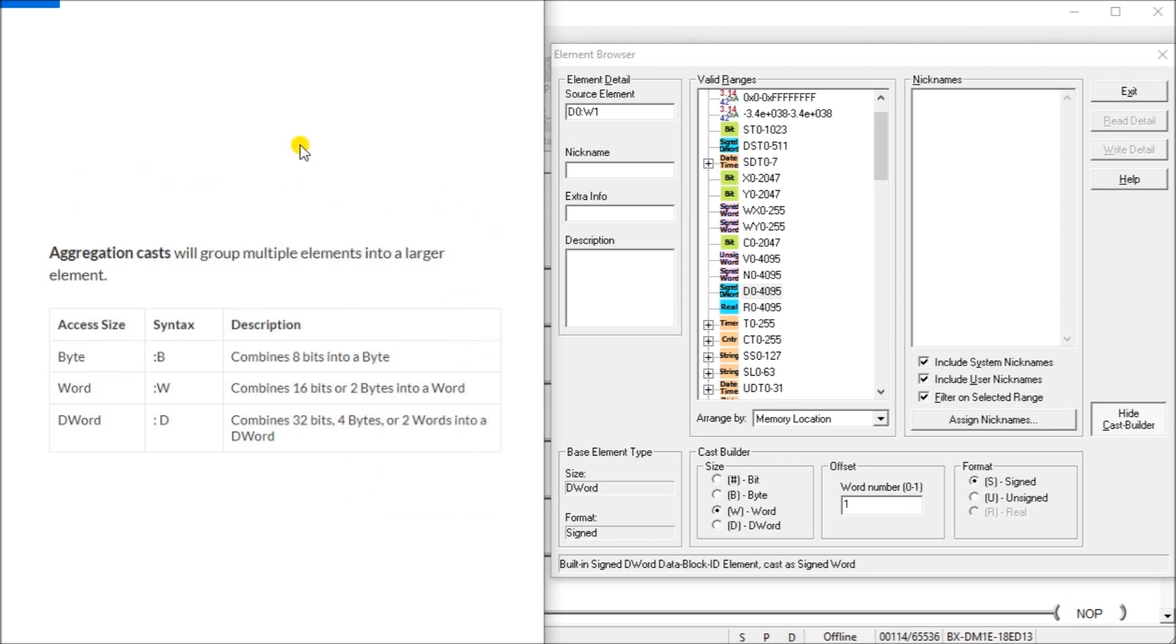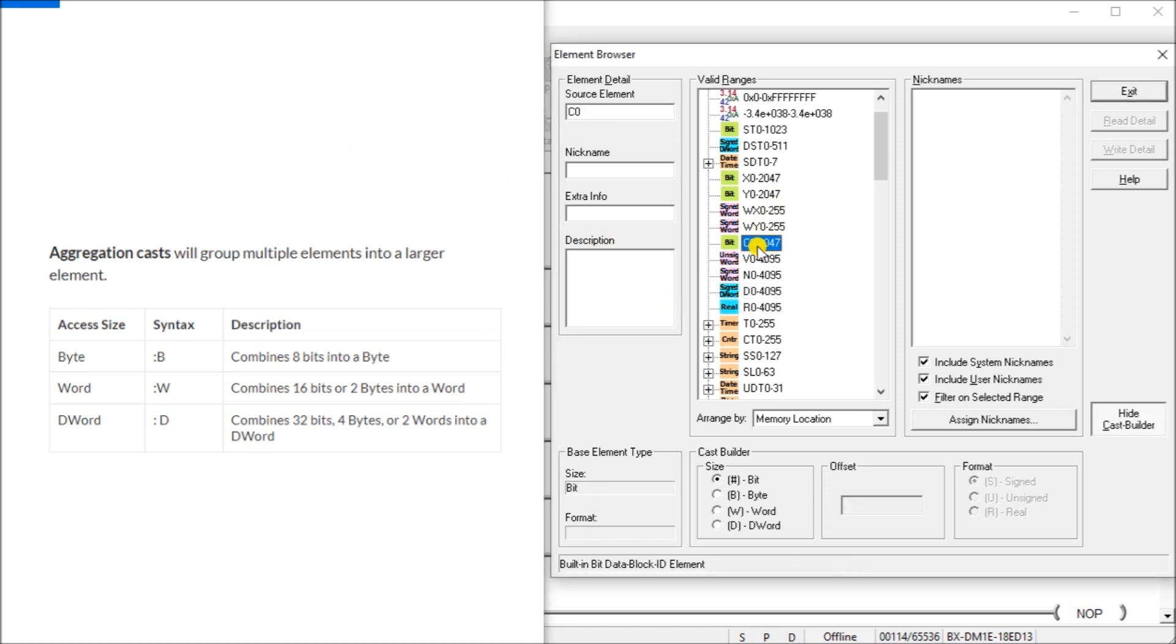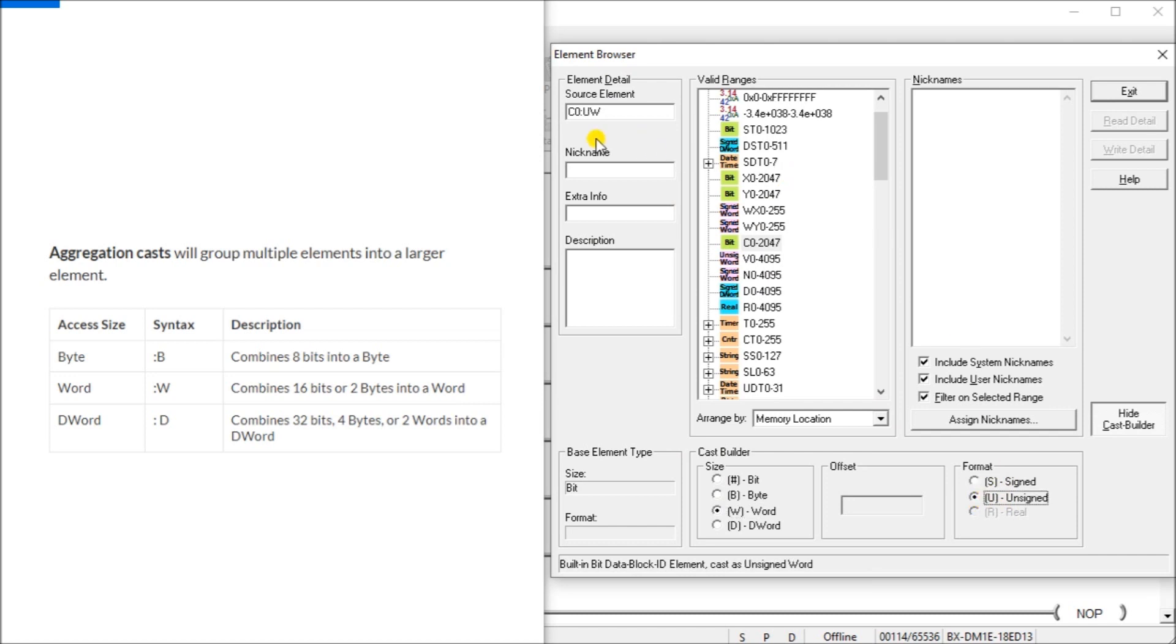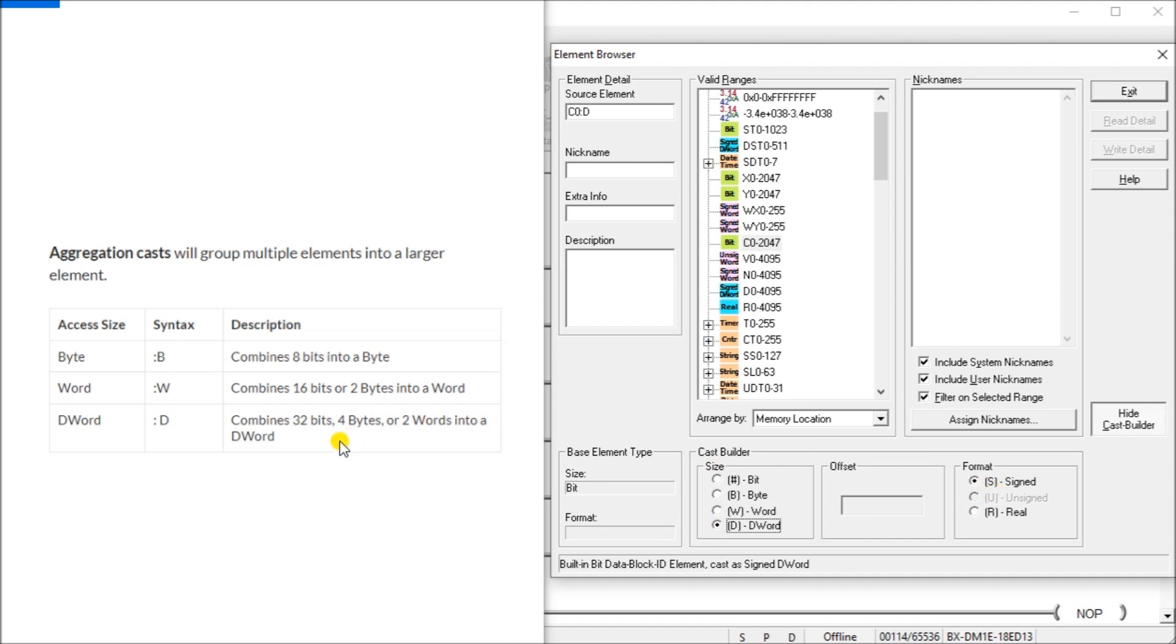Next we have aggregation casts, which group multiple elements into a larger element itself. So if we looked at say C0, we can then turn that into a word. And what it will do is we can then say it's a signed word or an unsigned word, turn into an unsigned word. So that's what we do. So we'll now take C0 to C15, which is the first 15 combines that into a 16 bit word for us. We can also go a double word and it will take and turn into a signed word. So we'll take 32. So the first 32 bits starting at C0, and now that combines into a double word for us. So aggregation groups them together.